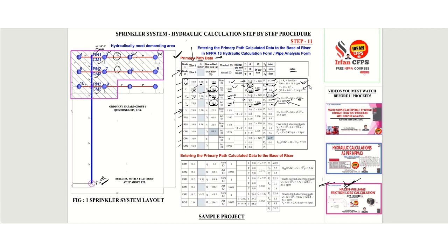For Node 3 to RN1, we entered the data and calculated the small q and capital Q. The nominal ID is mentioned, and there is one tee fitting with an equivalent length of 6 feet, making the total pipe length 13 feet. Using the friction loss formula, we get a friction loss of 0.266, and the flow calculated is 21.5 GPM.